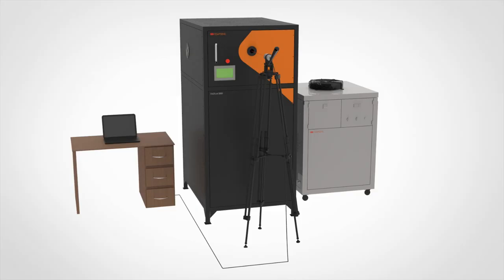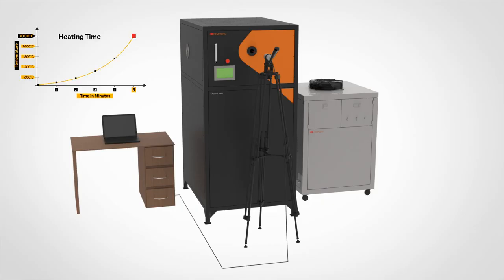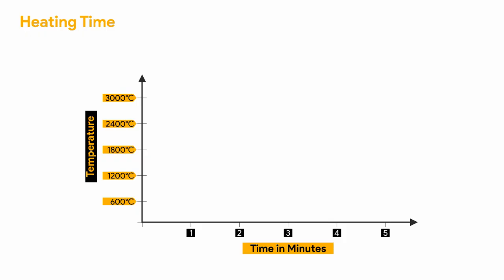Now, to perform calibration using the FASTcal 3000, begin by aligning the pyrometers so that the laser is centered in the cavity. Once the pyrometer is properly aligned, set the desired temperature on the UI. Calibration data will be sent to the PC for accurate results.